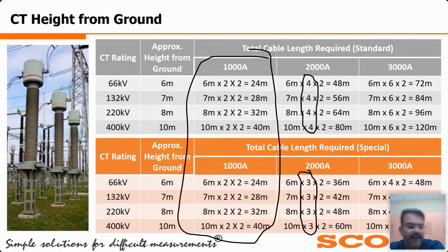So this is the way we are reducing the total length required for the cable. As we are reducing the length of the total cable, we are able to reduce the total weight. One more thing, as I have mentioned in the chat, is that these special cables come with special insulation, also known as class F insulation with high flexibility. This highly flexible class F insulation is fire retardant.